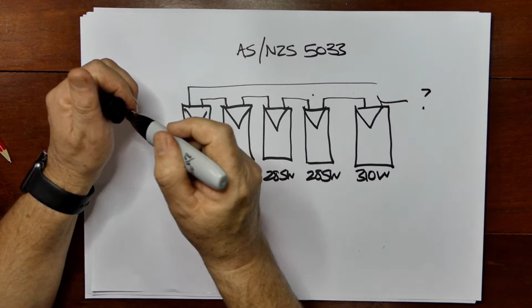When you're adding panels in a string, you are increasing the voltage. If you add a bigger panel, it depends on how many cells it has as to how much voltage it adds, but more importantly is the amount of current it can produce. What you don't want to happen - it's all about current. Let's say these panels have an operating current of 8 amps, so these are all 8 amps. This 310 watt module, even though it's more powerful, might actually have smaller cells but more of them, and therefore a higher operating voltage. So it gets its higher power by having more cells - it might be a 72 cell module, where these might be 60 cell modules. So let's say this one actually produces only 7 amps, but at a higher voltage.